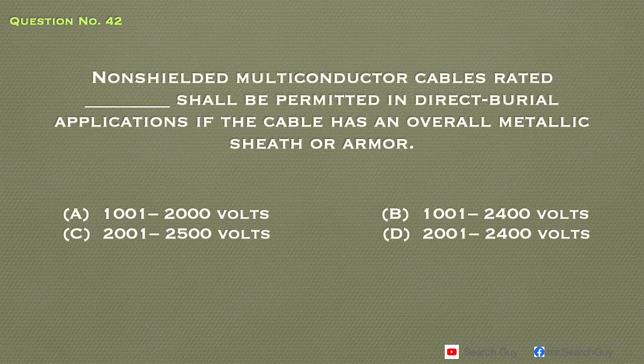Question number 42. Non-shielded multi-conductor cables rated blank shall be permitted in direct burial applications if the cable has an overall metallic sheath or armor. A. 1001 to 2000 volts, B. 1001 to 2400 volts, C. 2001 to 2500 volts, D. 2001 to 2400 volts. Answer: D. 2001 to 2400 volts.